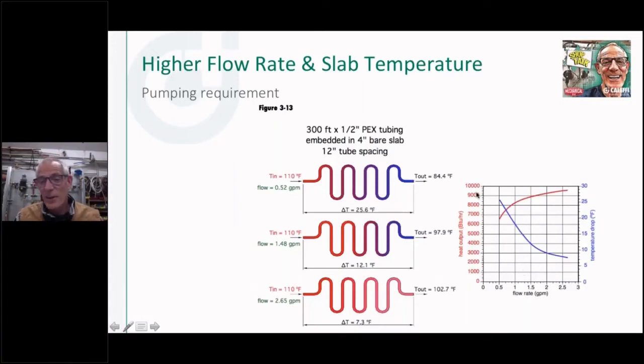And so there it is right there. You can see as my flow rate changes, you can see how the output of that slab changes. Now notice on the red curve up there, you get to the point where a lot more pump gets you very little bit more output. So you can see I've got a pretty steep curve going up, and then when I start to get out here, and this is kind of the difference between a 1 gallon a minute and a 4 gallon a minute on a fin tube baseboard, you get a little bit more output, but is it worth the extra pump to do that? You just got to run the numbers and know that, but you're going to get to a point where this is going to start to flatten out. Even if I went out here to 3-4 gallons per minute, I'm not going to get that much more output, but it's going to start gobbling up a lot more pump horsepower to get you there.